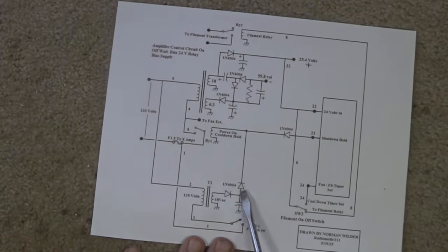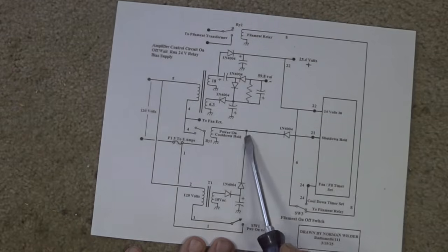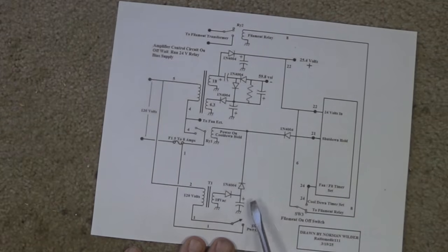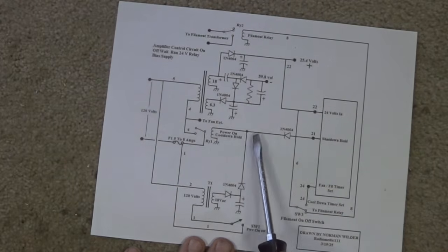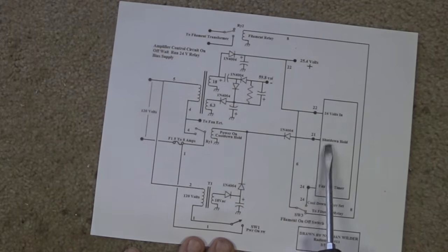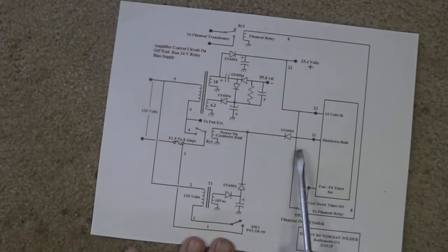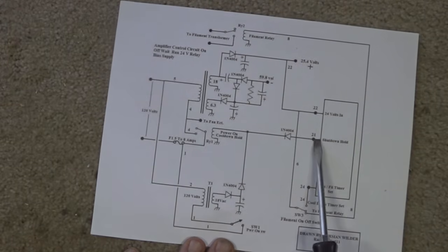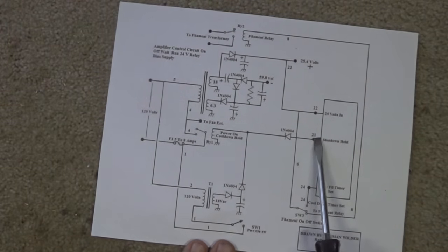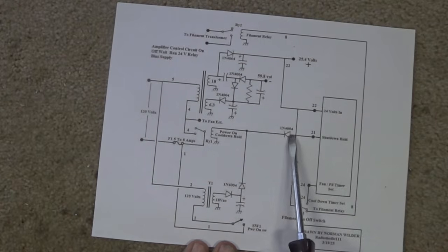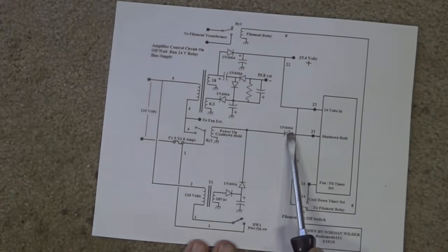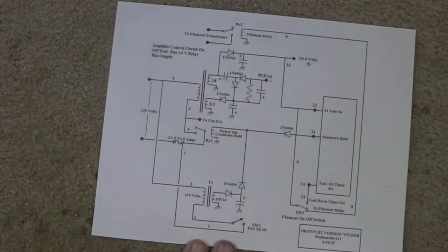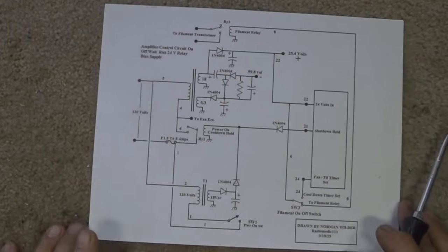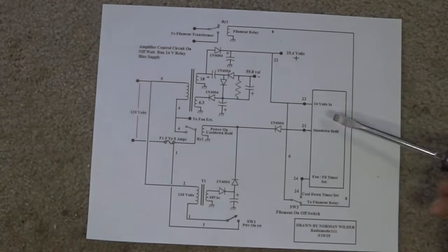This one simply keeps the 24 volts going toward the relay. And since it's going to the relay, we don't need it coming back in here. In case something else is tied on this, you wouldn't want it kept activated when we're trying to turn the unit off. So we have, I guess you'd call them steering diodes.